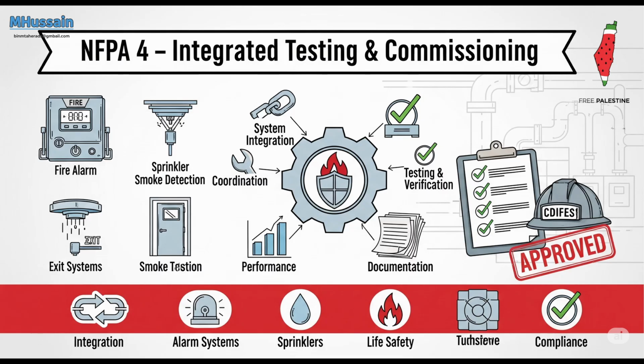So what kind of qualifications does the ITA need? They need to have demonstrated skills, experience, or knowledge related to the design, installation, operation, and maintenance of the specific type of fire protection and life safety systems that are installed in that building. So they need to understand how these different systems are supposed to work together. Precisely. It's not necessarily about knowing every single wire in the fire alarm panel, but understanding the overall integration, the sequence of operations, and where potential failures might occur in that interaction.